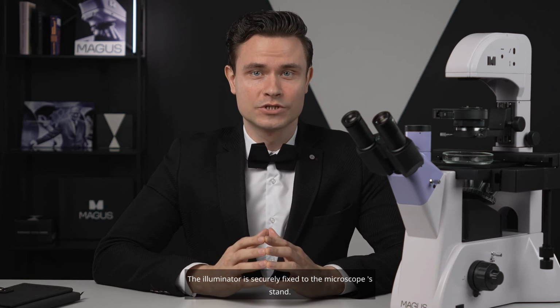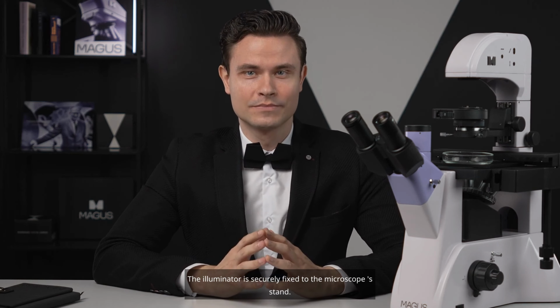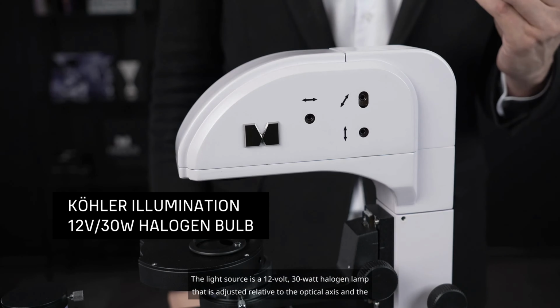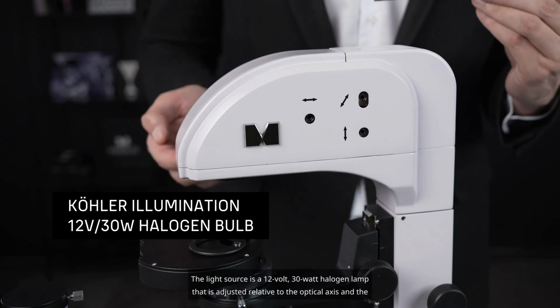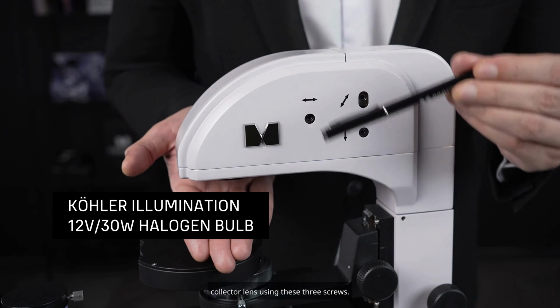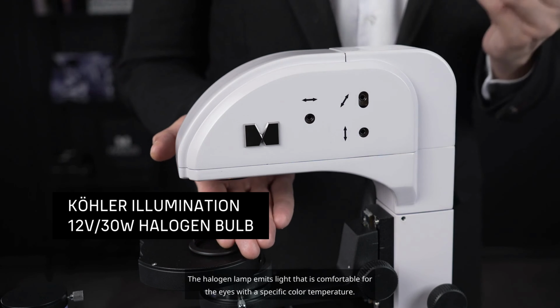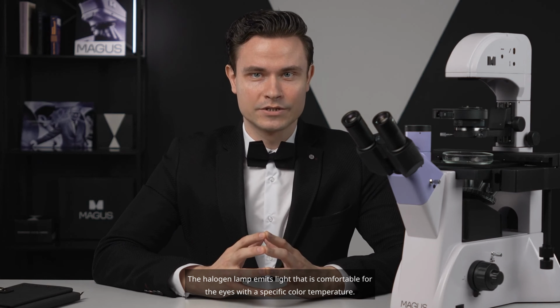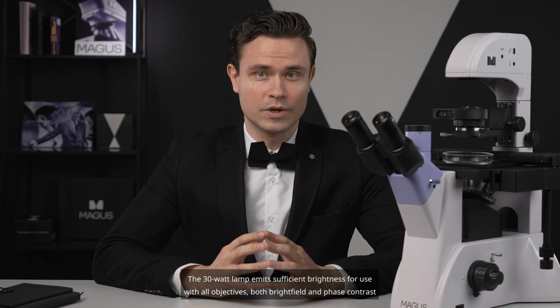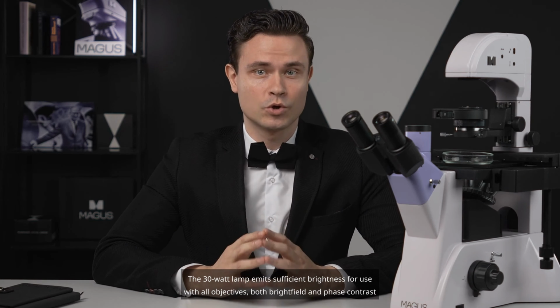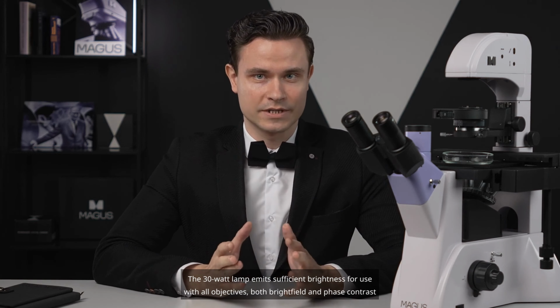The illuminator is securely fixed to the microscope stand. The light source is a 12-volt, 30-watt halogen lamp that is adjusted relative to the optical axis and the collector lens using these 3 screws. The halogen lamp emits light that is comfortable for the eyes with a specific color temperature. The 30-watt lamp emits sufficient brightness for use with all objectives, both bright field and phase contrast.